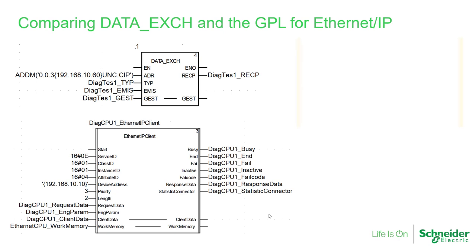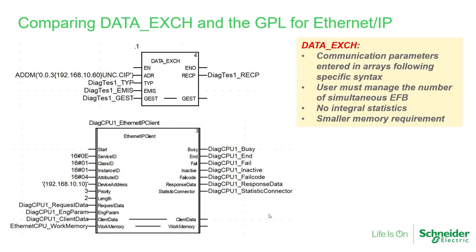Comparing the two methods: for the data exchange function block, communication parameters such as class, instance, and attribute must be passed to an array following a very specific syntax through the fourth input pin. Also, the user must manage the number of simultaneous queries being sent, so additional PLC programmer logic may be needed to control how the data exchange function blocks are triggered.